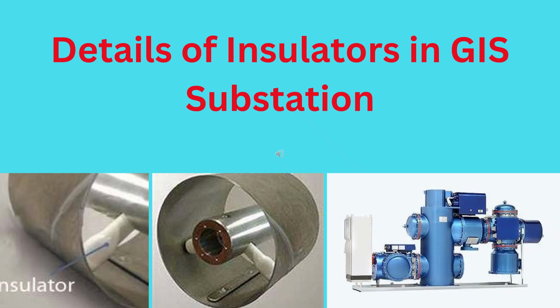Parts on the interior of the GIS are supported with cast epoxy insulators, which allow for a gas barrier between parts of the GIS or are cast with holes in the epoxy to allow gas to pass through from one side to another. These support insulators are made of an epoxy resin which is carefully cast to avoid the formation of voids or cracks during the curing process. The high-graded epoxy resin material is formulated and the insulators are shaped for optimizing electric field distribution, mechanical strength, resistance to surface electric discharge, and for the convenience in manufacturing and assembly.